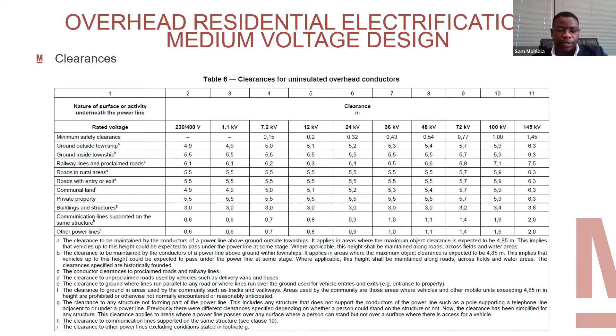This clearances table shows the clearances for uninsulated overhead conductors. From the left, we have minimum safety clearance, ground outside township, ground inside township, railway lines and proclaimed roads, roads in rural areas, roads with entry or exit, communal land, private property, buildings and structures, communication lines supported on the same structure, and other power lines. There are different voltages and minimum clearances required. This is a very useful table to use when designing.